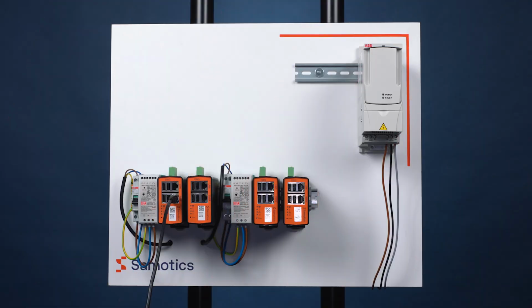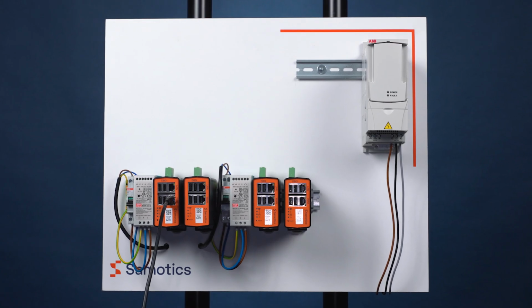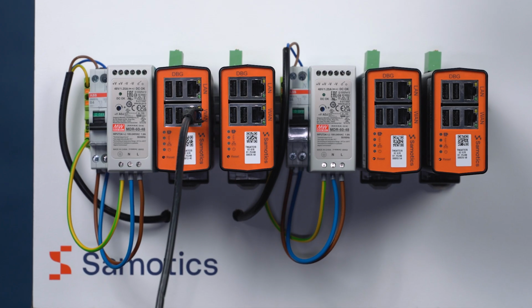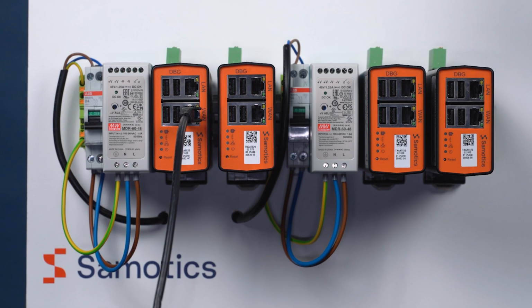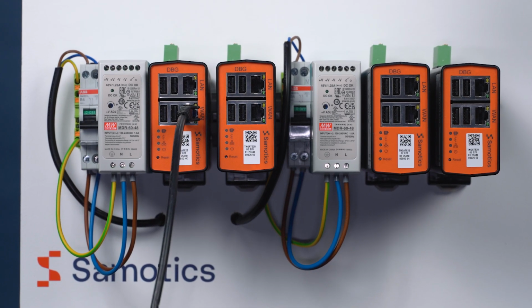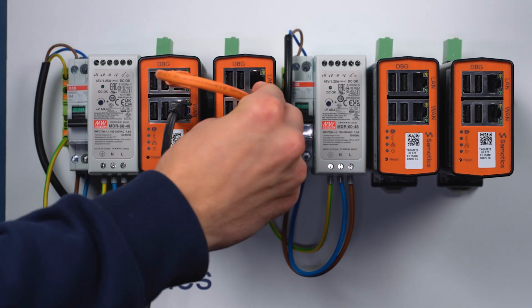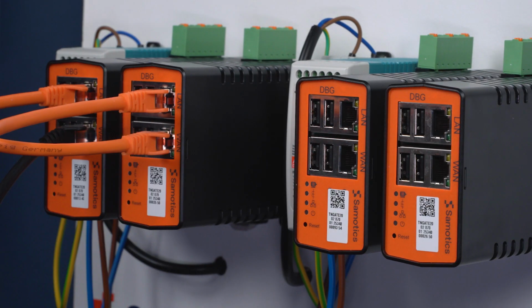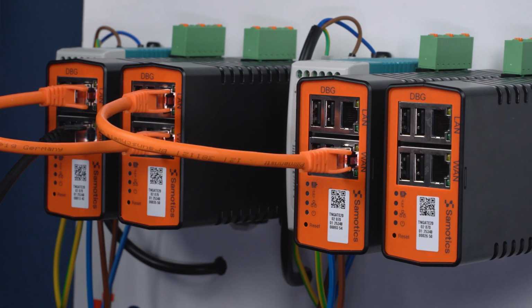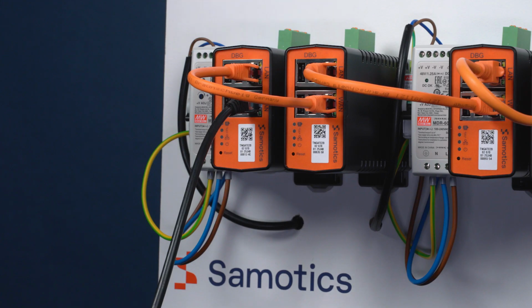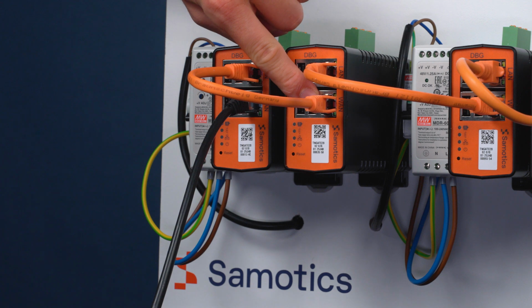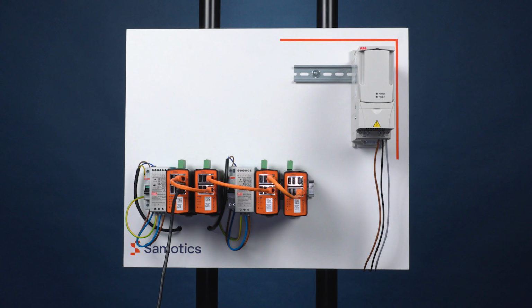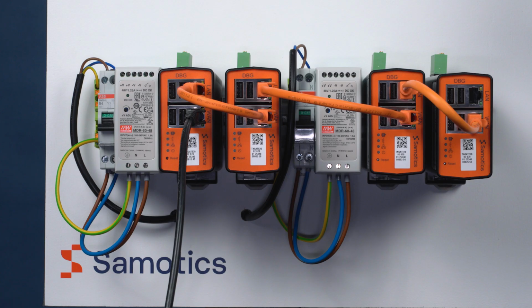You can connect multiple NOVAQ units to share power from the power supply unit using Power over Ethernet. All required power supplies and their placement in the chain are provided by Samotics. To set this up, connect an Ethernet cable from the LAN port of the NOVAQ linked to the power supply to the WAN port of the next NOVAQ. When chaining, always use the top port for the NOVAQ closer to the power supply and the bottom port for the NOVAQ further away. Depending on the amount of NOVAQs and the distance between them, additional power supply units will be included.